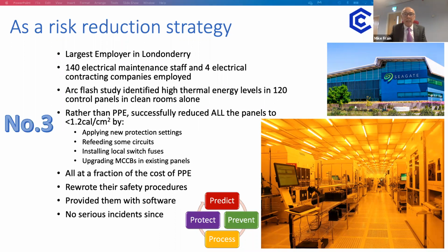There was a lot of Square D on that particular site, and basically the Square D circuit breakers, when it was built, weren't quite as sophisticated as a new one, but actually you could do a straight swap. So the new ones had adjustable instantaneous pickup levels, and we were able then to just tone those down a little bit, bearing in mind the load requirements and motor starting and so on. But the thing that I'm trying to put over here is that it was a fraction of the cost of PPE. Because actually getting PPE for clean room environments like that is very expensive. So that was a major driver, I must admit.